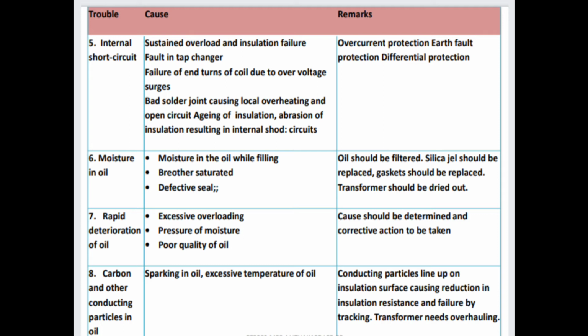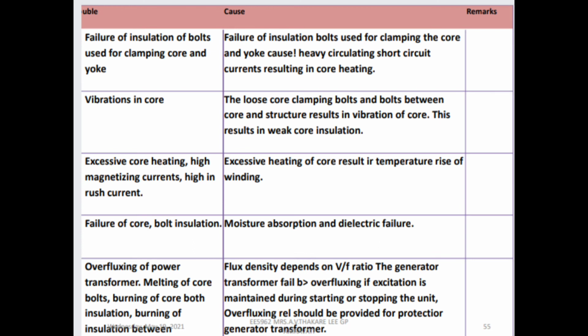Next trouble is carbon and other conducting particles in oil. Causes are sparking in oil, excessive temperature of oil. And the remark is, conducting particles line up on insulating surface causing reduction in insulation resistance and failure by tracking. Transformer needs overhauling. So the next trouble is failure of insulation of bolts used for clamping core and yoke. Causes: failure of insulation of bolts used for clamping the core and yoke causes heavy circulating short circuit current resulting in core heating.